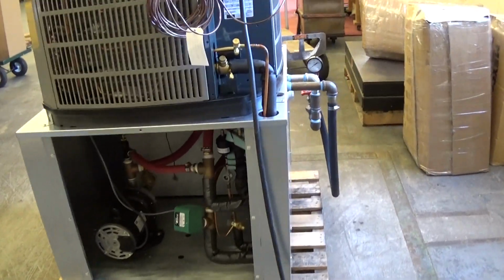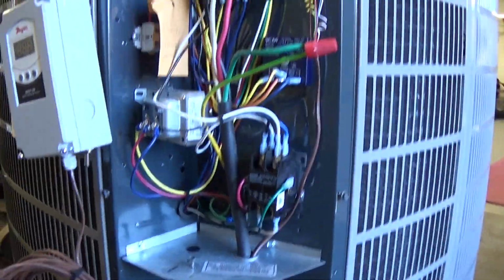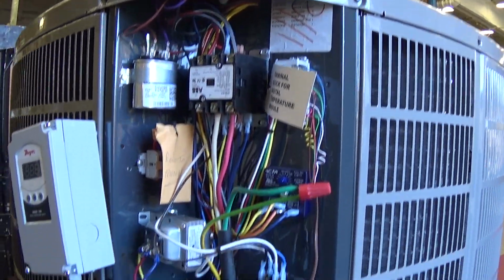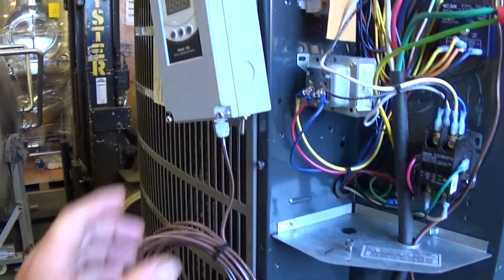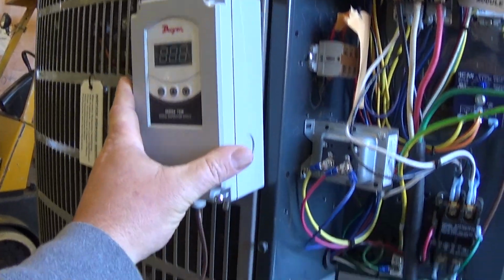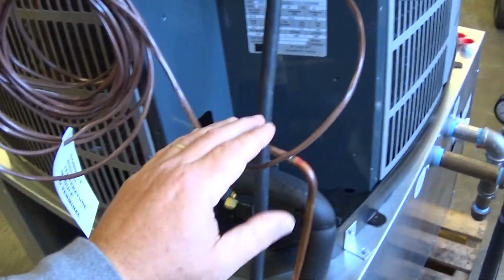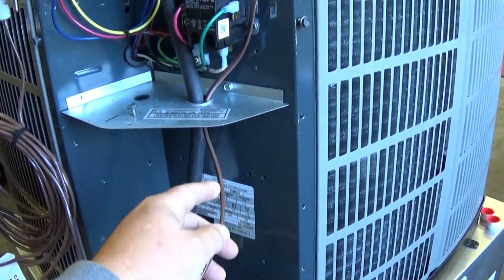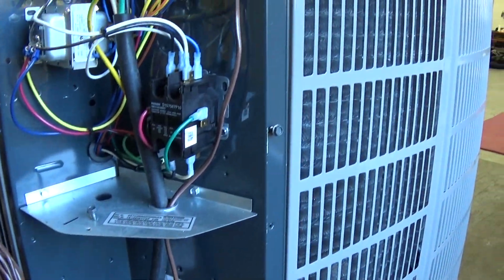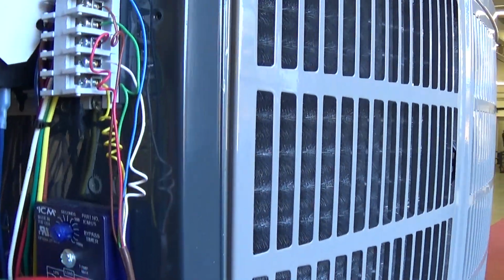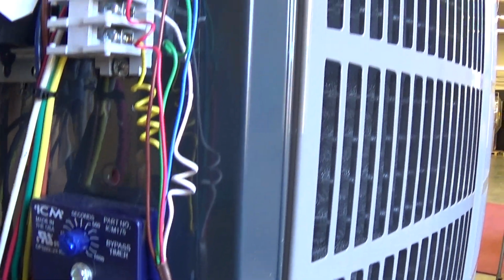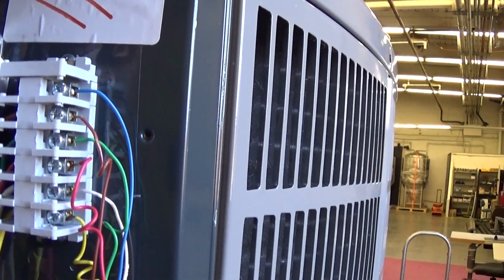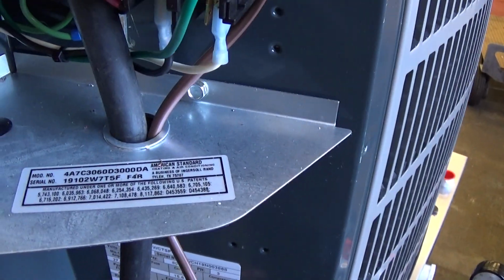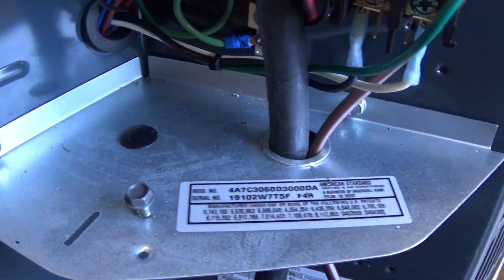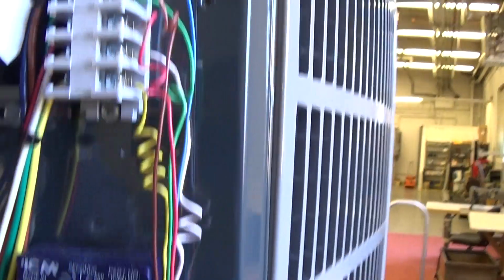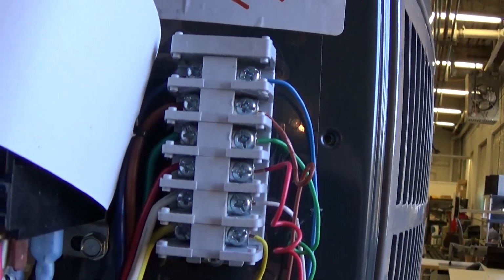So our controls are up here. Then that obviously will arrive with a metal shroud over that. The controller, this nice little Dwyer controller, will ship loose. It's on a 30-foot cable, so this is an outdoor chiller, but you can mount this controller remotely, and it's just simply color-coded. You just match up the wires on the right side here, which you would thread through adjacent to your controller power or your chiller power, and just match it up with the same color internal wires here.